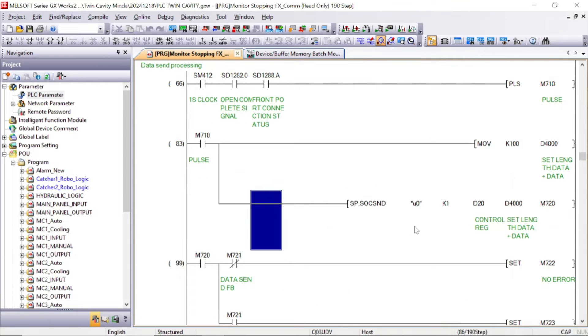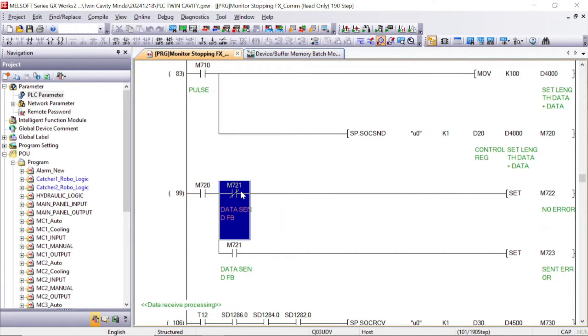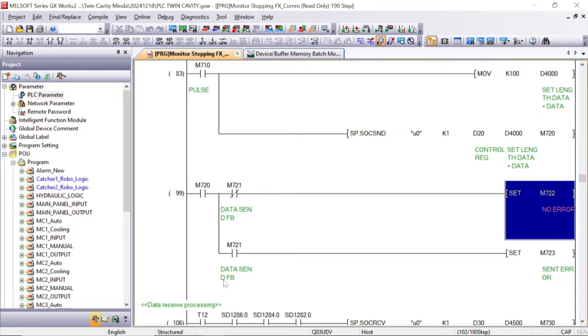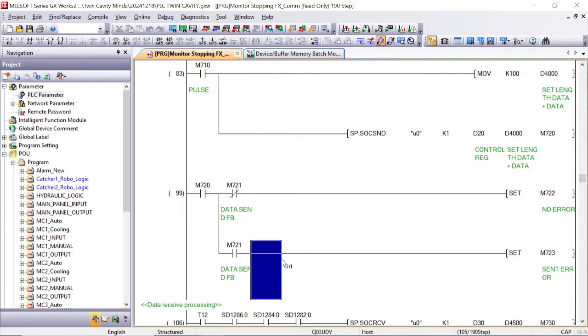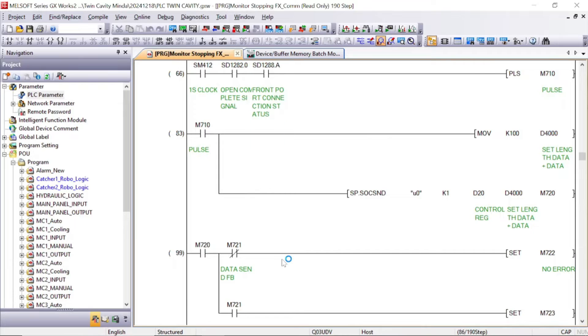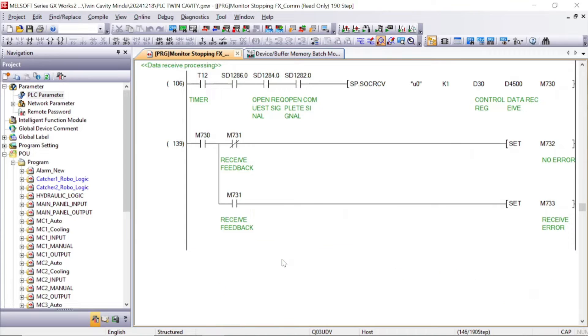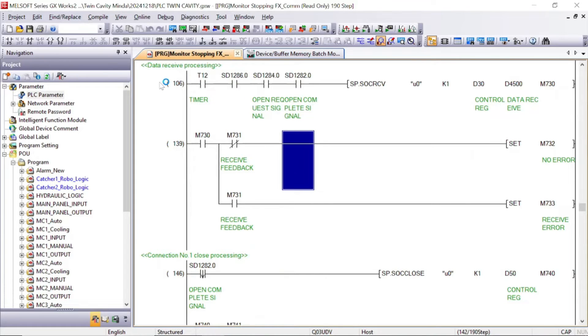This program is for the send data. If you take M720 bit, then M721 will give the feedback return. If M721 is off, there is no error for the send data; if this bit is on, then there is a send error. You can take this bit as a send error with alarm. That was the send data program.